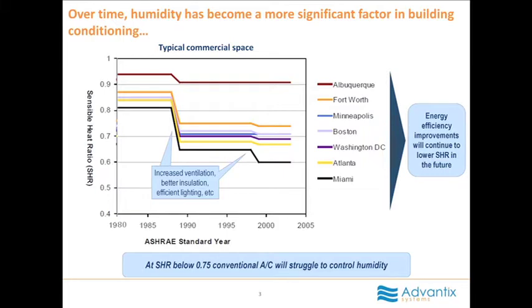And you eventually start seeing that over this selection of cities, if you're in a reasonably humid geography, and I guess this might be the closest analogy for us here at Fort Worth, or maybe Atlanta was brought up earlier, you're no longer up here in that area where it's 80% sensible or 80% temperature reduction. You're talking more between about 3/4 and 2/3. And by the way, this trend will continue.